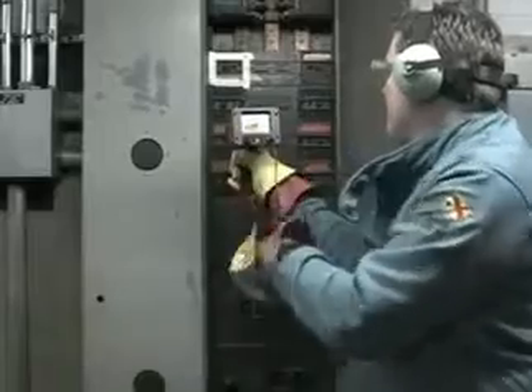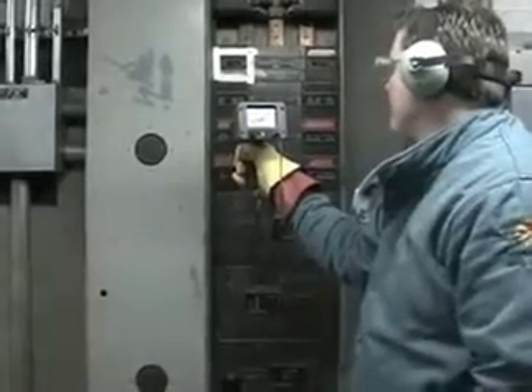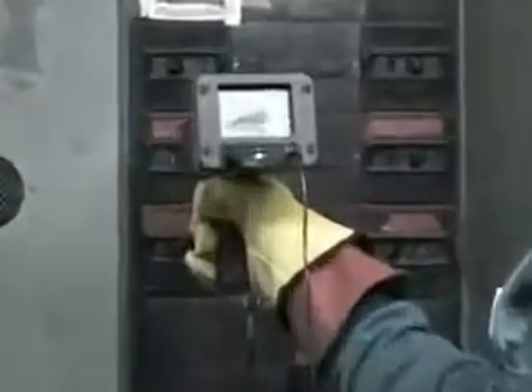Here the ultrasonic probe identifies noise within a breaker. As the technician moves further into the service, he'll give special attention to identifying what the problem is and why it's occurring. He'll then document in detail all of the data within the TEGG tasking software.